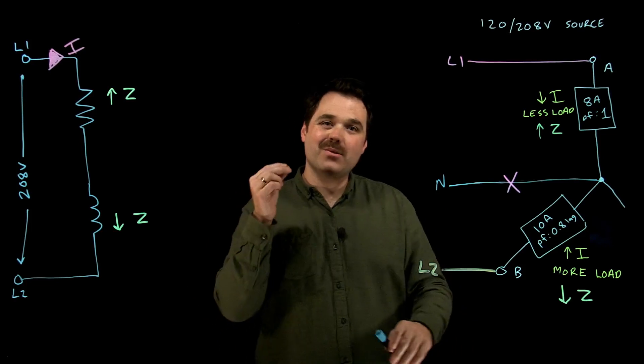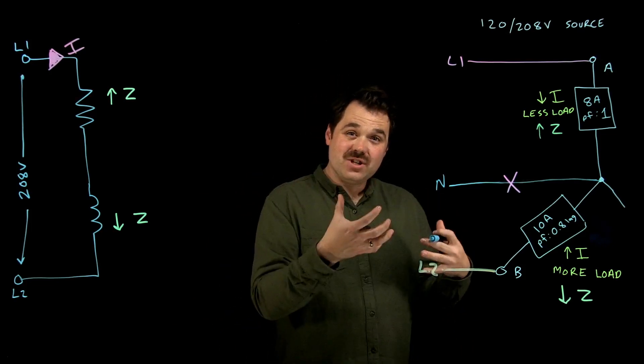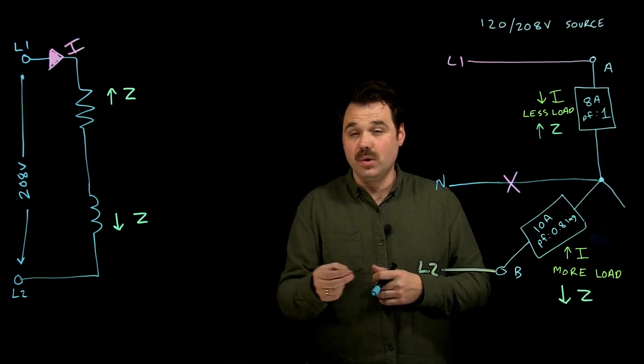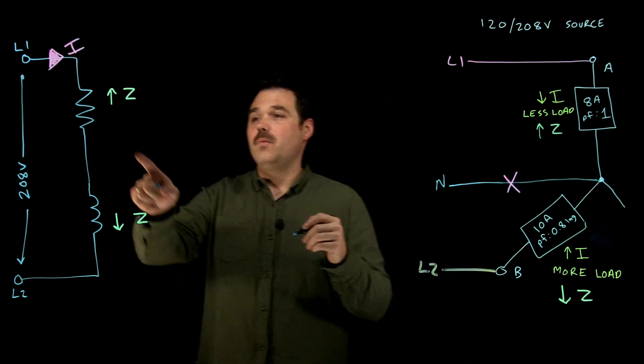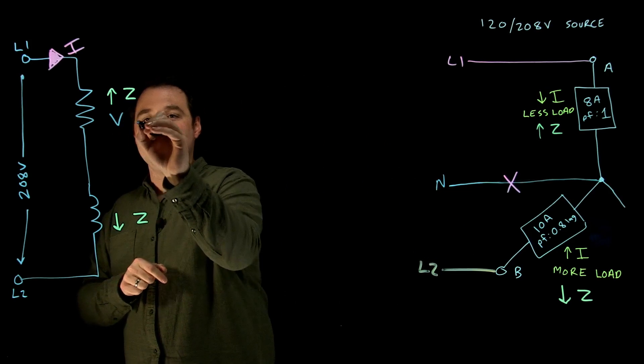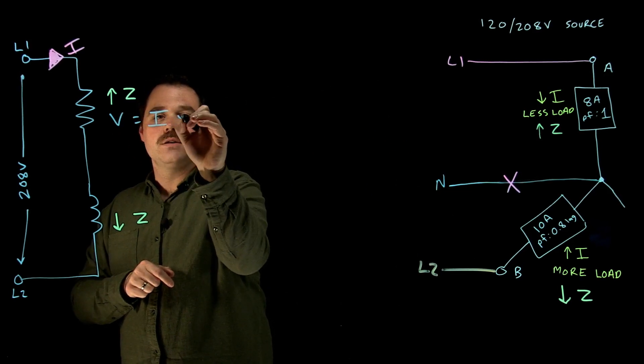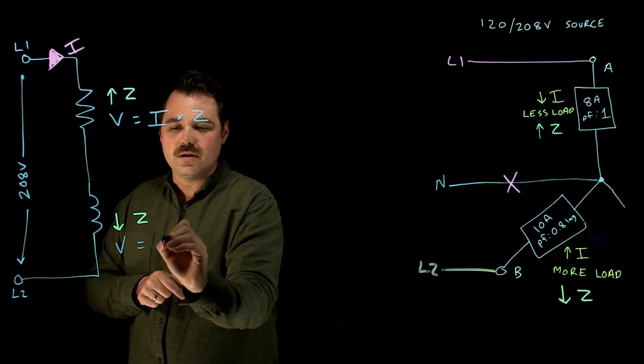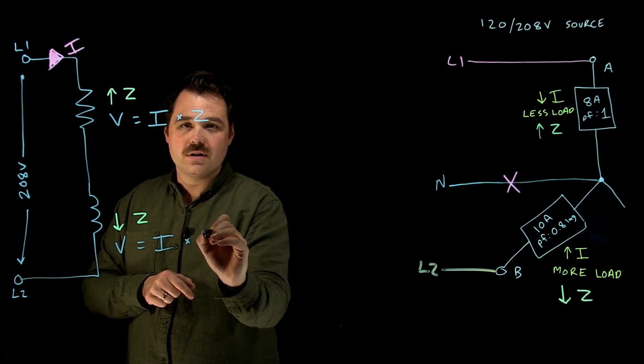What we care about is this: what changes when my neutral breaks is the voltages. We are no longer maintaining phase voltages. In fact, we are going to have a volt drop here, V equals I times Z, and we are going to have a volt drop here, V equals I times Z.